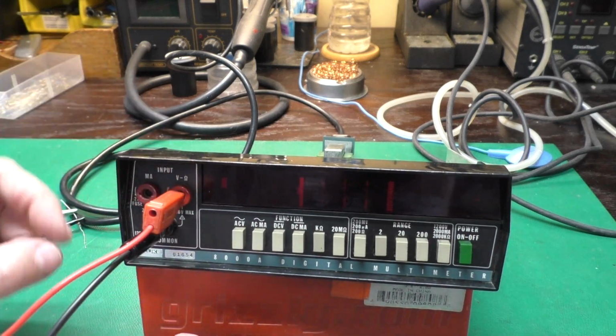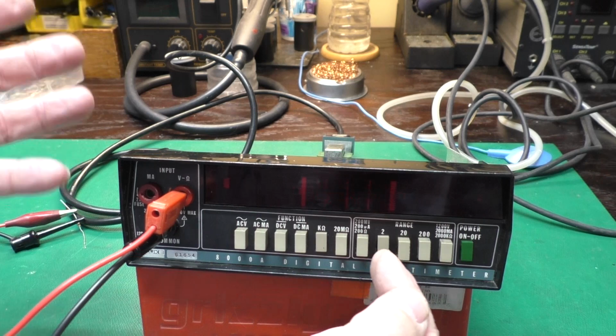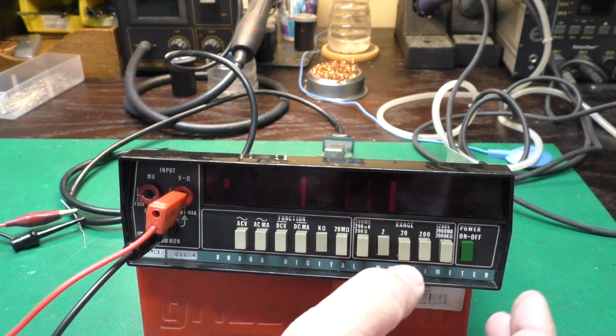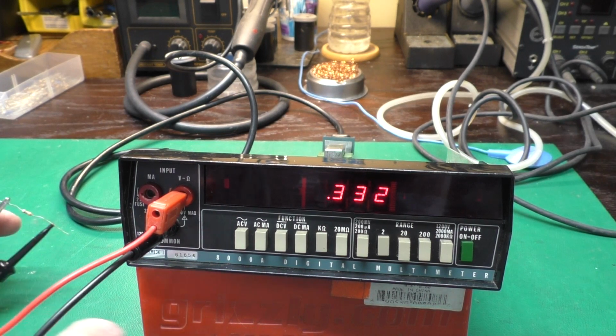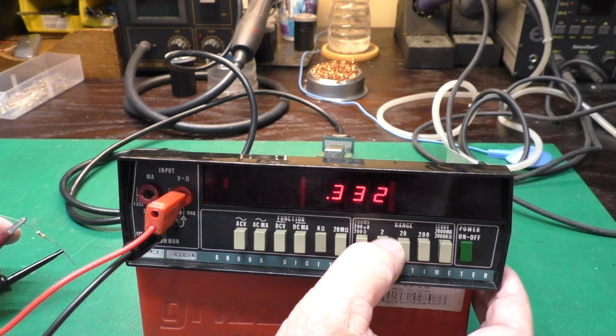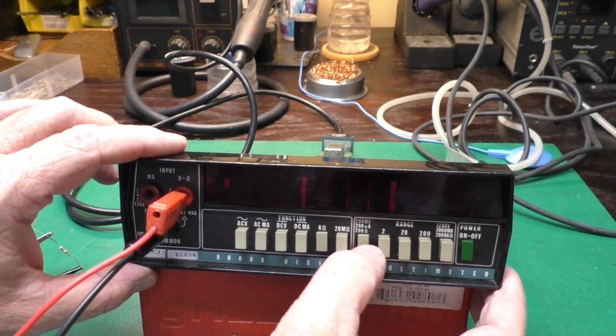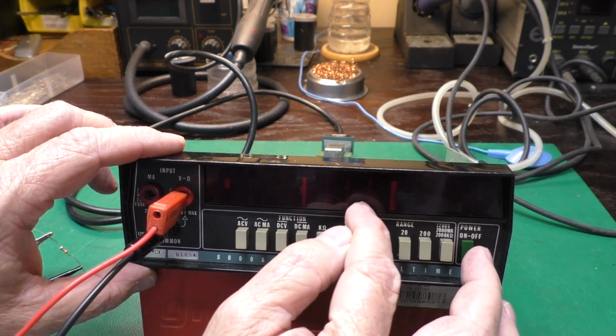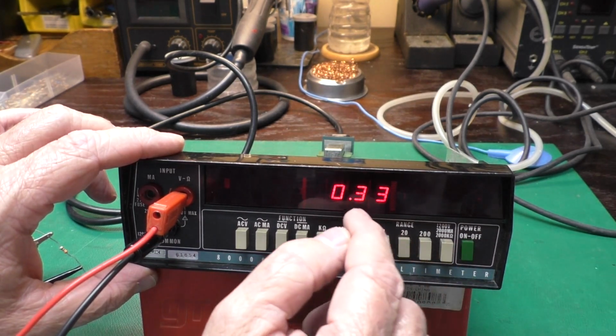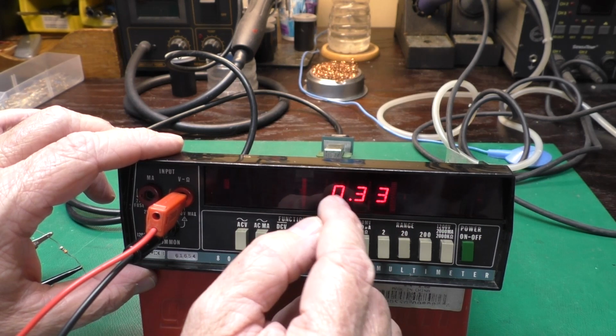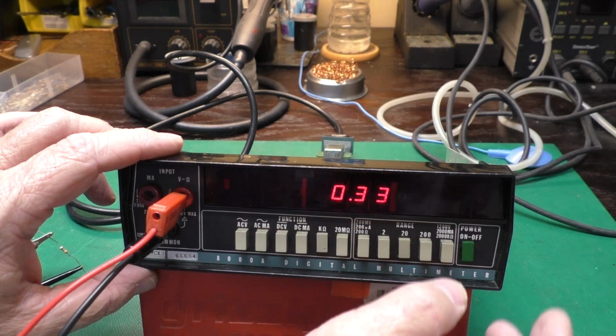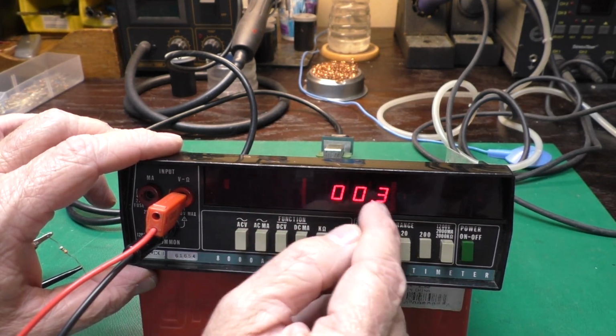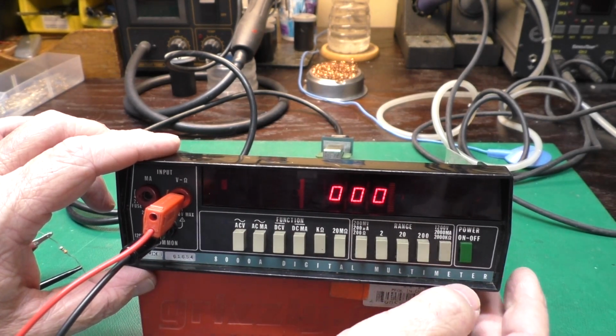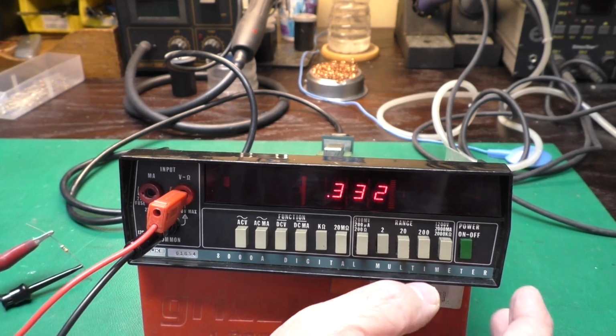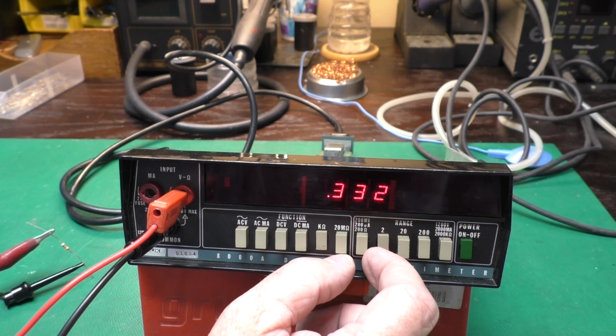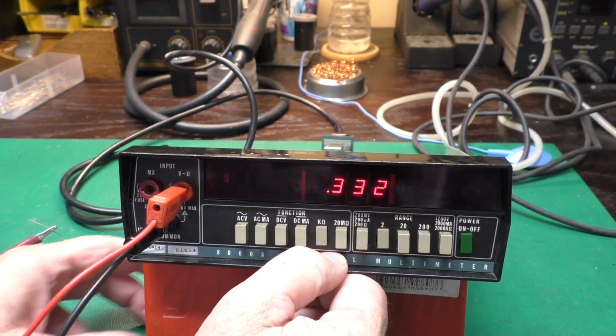And let's see how this guy works. And this is the one that's got the good fuse holder. So you can see we're on resistance measurement here, and it's measuring open load. I'll connect the 330 ohm resistor. It measures 332 ohms. We're on the 2K range, 200 ohm range. We're out of range again, but you can see the decimal point moved, and we only have the 1 decimal point on now. 20K range. Our decimal point has moved, but we lost one digit because we've got the leading 0. And same here, now we've got 2 leading zeros, so our decimal point moved that way. Now we lost it all together. So flushing the switches out really good on this one took care of that decimal point problem. And this one is a good meter. Everything works really well.